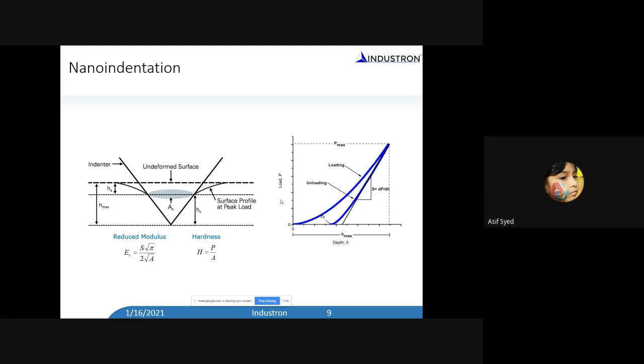You are taking a probe and you know the shape of this probe. I said 3-sided pyramidal probe, but the tip end is something whose shape you don't know. It's normally spherical. But by doing calibration on a known sample, for example, a fused quartz sample for which the modulus of the material is known, you do an indent and you measure the stiffness from the unloading curve of the load displacement curve. You load and unload, this is the typical load displacement curve. And from the unloading curve, this is the load, this is the displacement. If you take a slope, it's basically stiffness, right? So you measure the stiffness from this unloading curve.